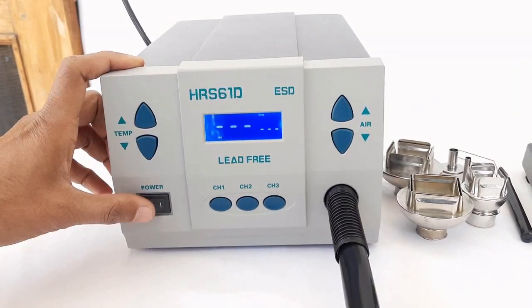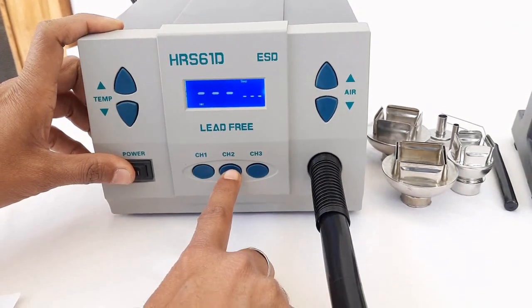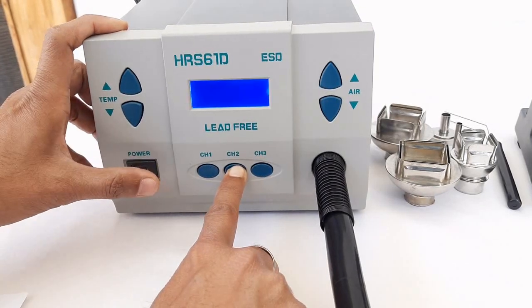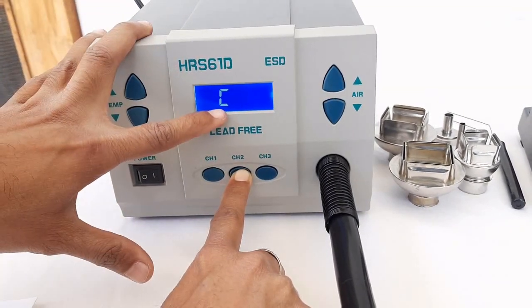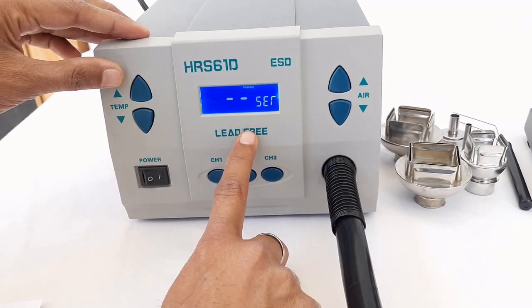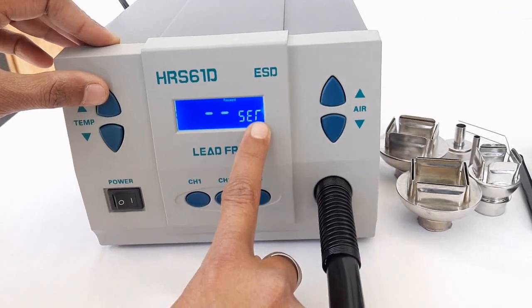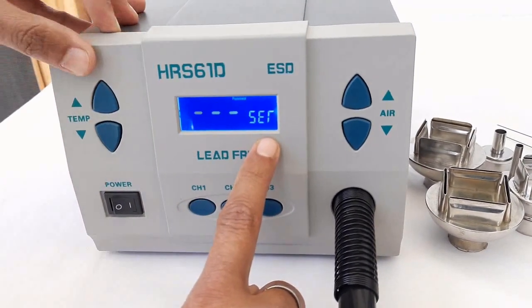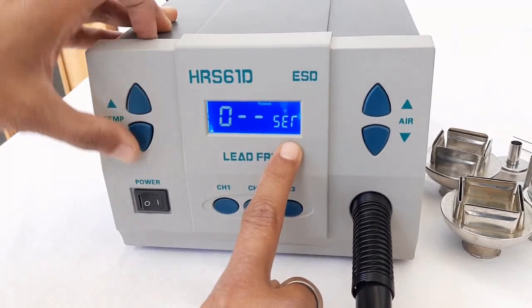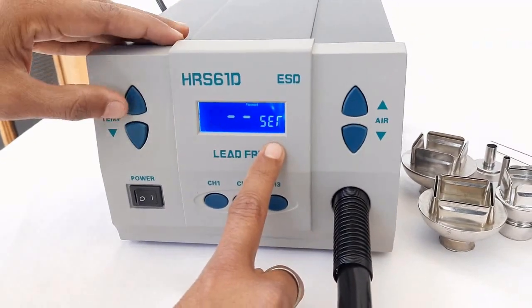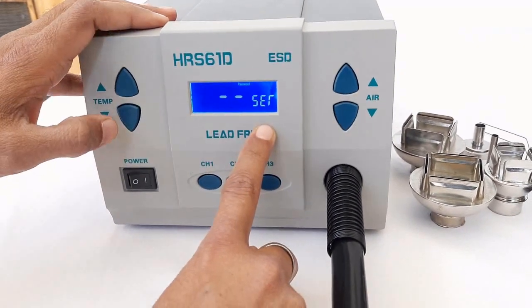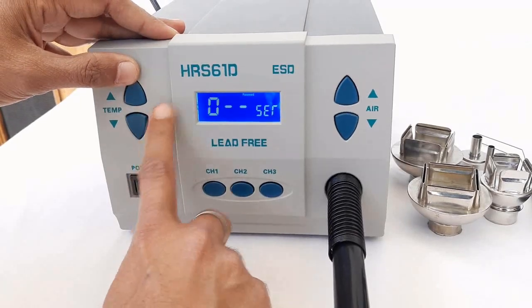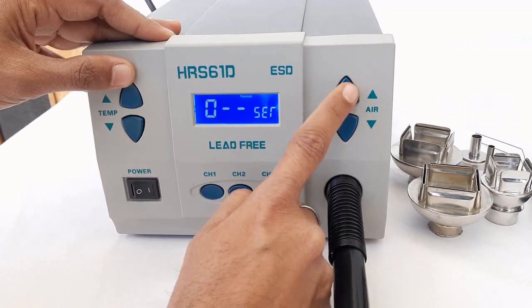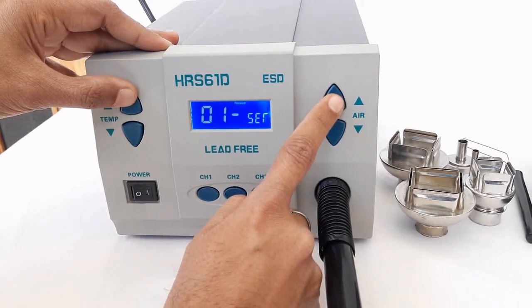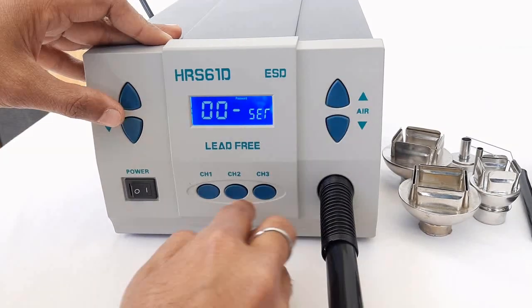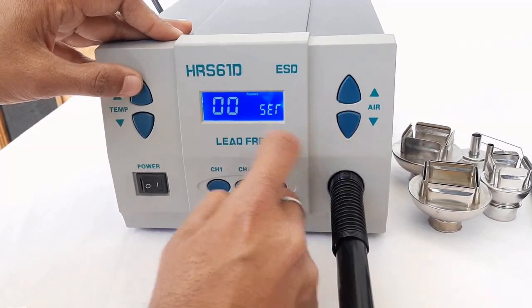First we need to switch the unit off, then press this channel 2 key and switch the unit on. First we will see a C displayed on the LCD, then SET will be displayed. Now we will use the up temperature or down temperature key to select a password of our own choice. Suppose we want to use a password of 007, first we select 0. Then to move the cursor to the next level, we use this up key, and again use the up or down button to select 0. Then again press the up key to move to the next step.